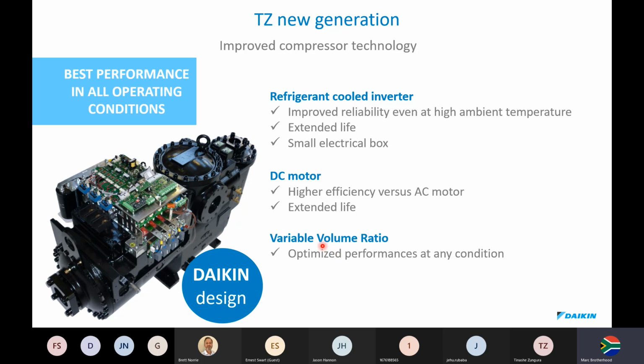And another unique design there, once again, is the variable volume ratio, which will optimize compression, internal compression. Remember, the higher the compression ratios, the more electricity I have to use. So if we don't need to over compress, we don't have to. We're continually modulating the internal pressure of the compressor.